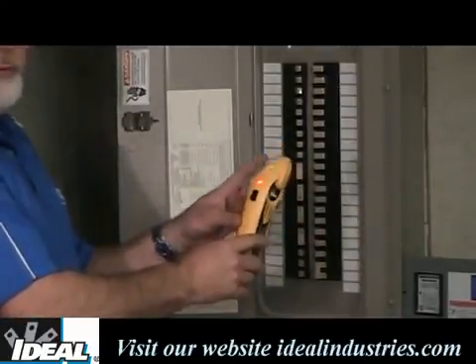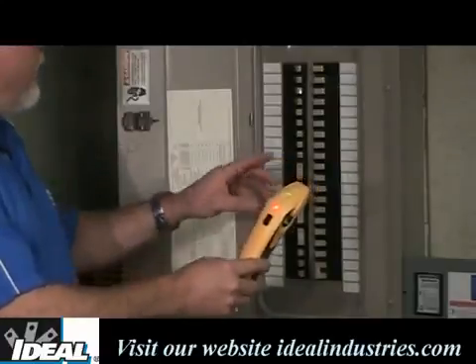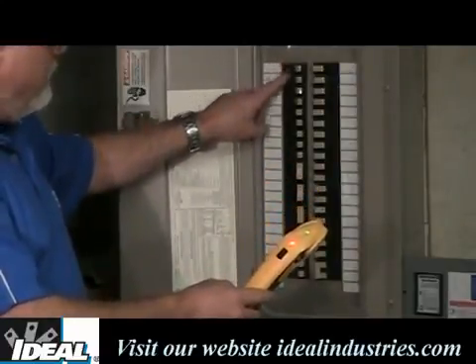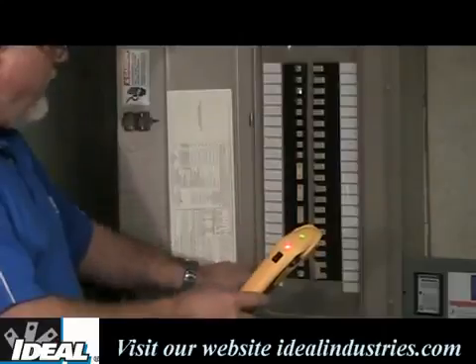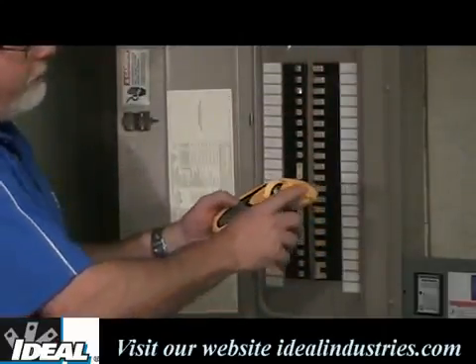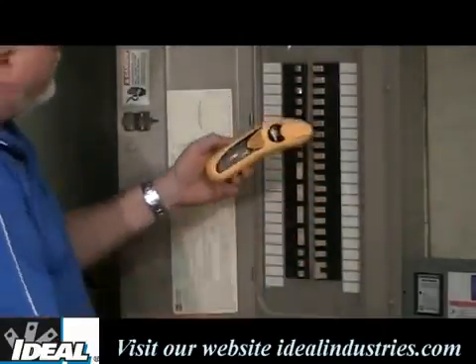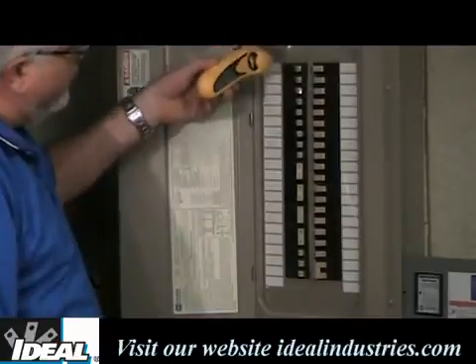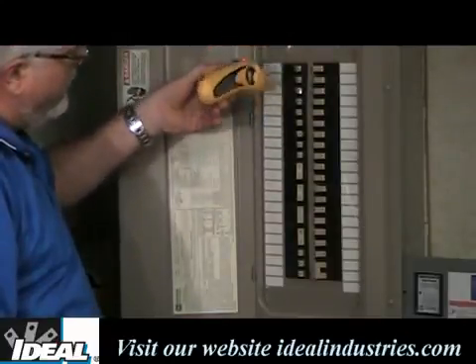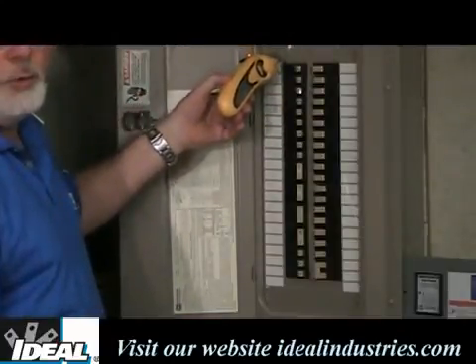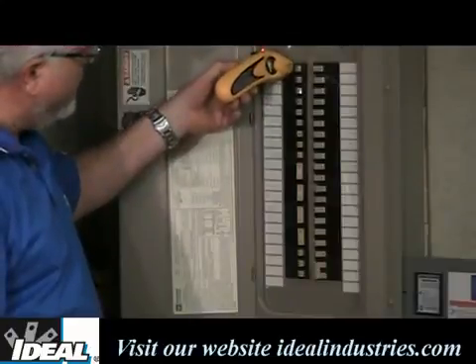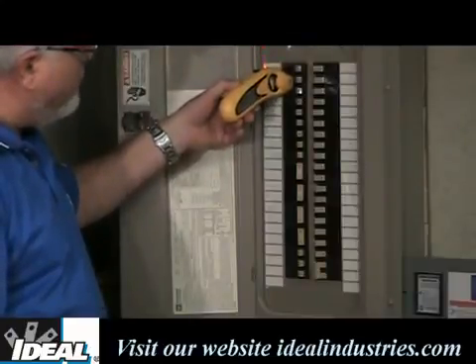When you hold the receiver up to the breakers, be careful to hold the tester flush with the face of each individual breaker. We're going to make sure the nose of the receiver passes over each of these. If you're at an odd angle, it's not going to give you a good reading. So hold it up flush, and it's going to start beeping at breakers.